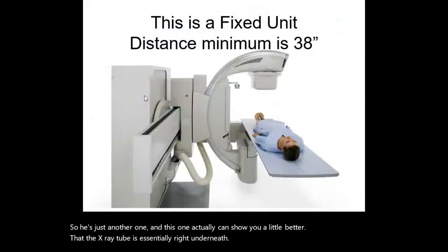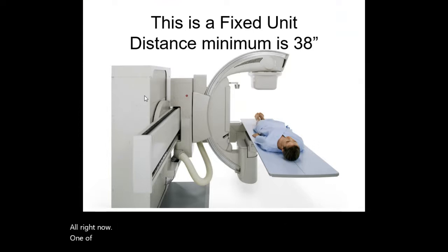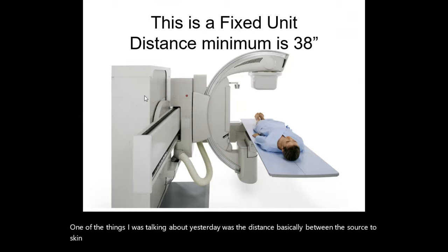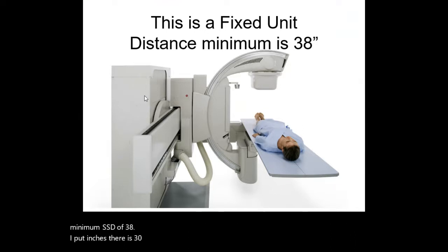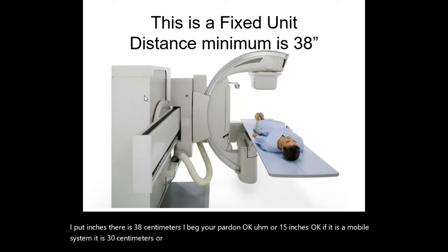All right, now, one of the things I was talking about yesterday was the distance between the source to skin. And I looked it up. When you're talking about a fixed unit, a fixed unit has a minimum SSD of 38. Oh, I put inches there. It's 38 centimeters, I beg your pardon, or 15 inches. If it is a mobile system, it is 30 centimeters or 12 inches. I just wanted to make sure I got that because I put it on one PowerPoint, it said 36, another one said 38.